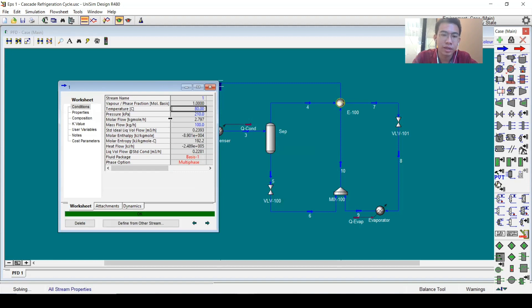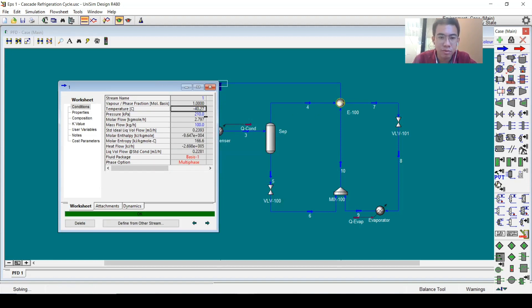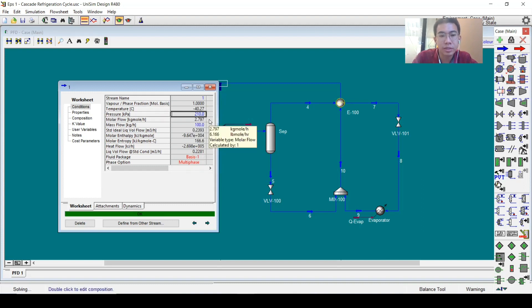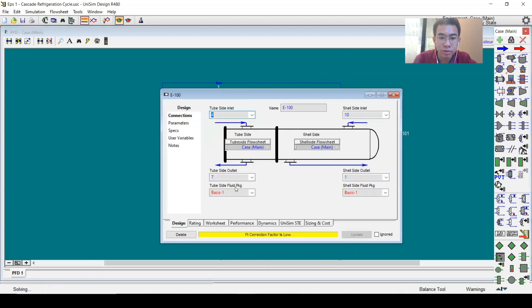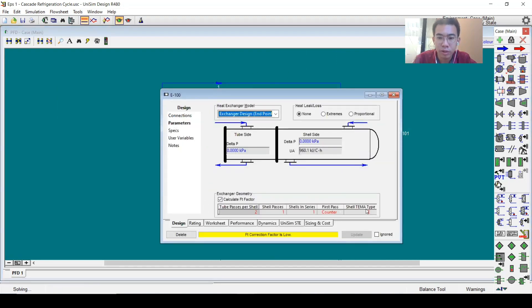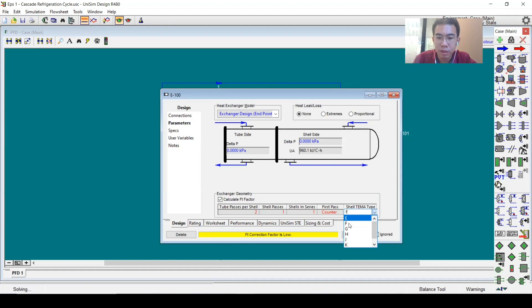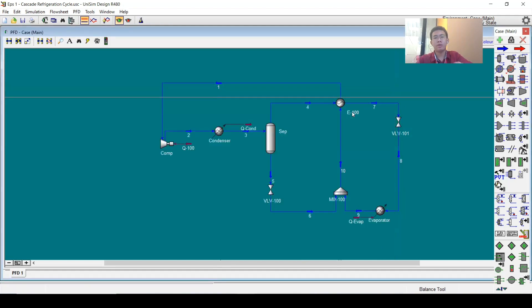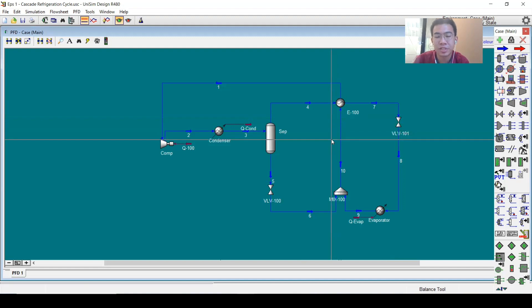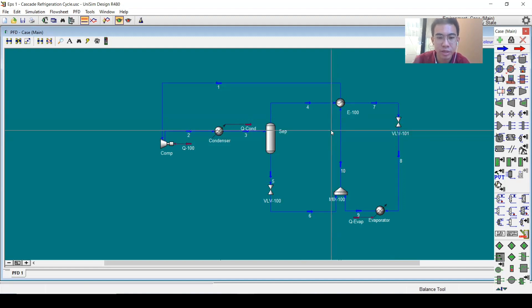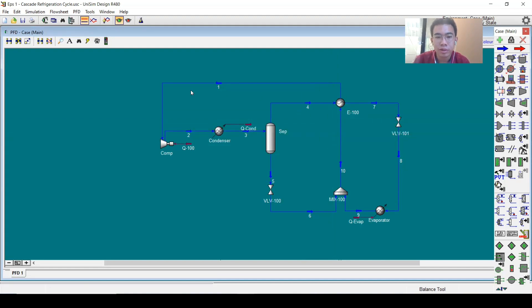You will see here that it is over-specified. Of course, because in number one we specified a lot of things. So we can delete the temperature—it will calculate—and we could delete this as well. We could see that the FT correction is low, so we could change the TEMA type to F, and we're done.